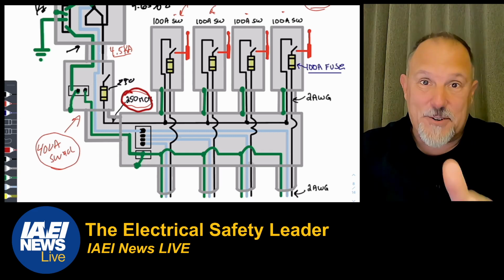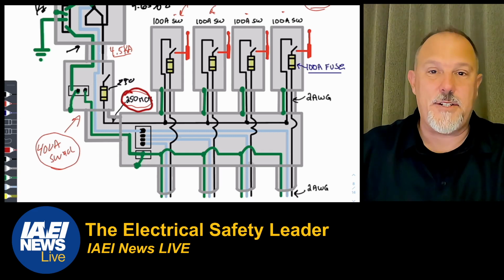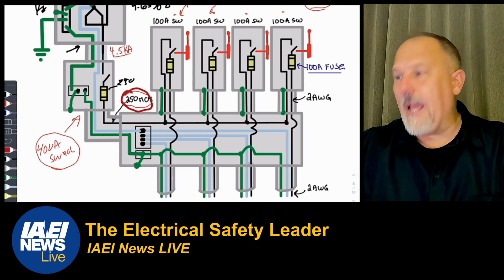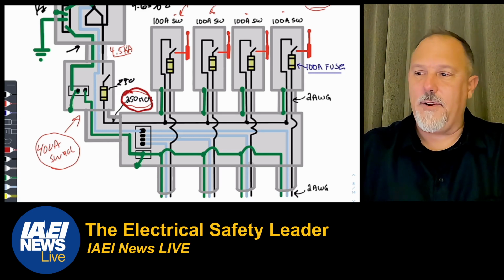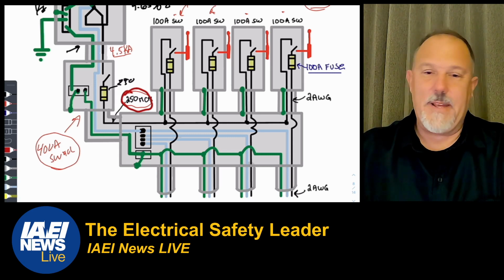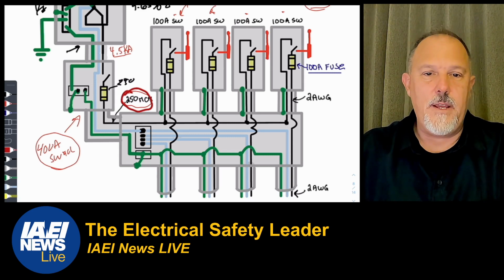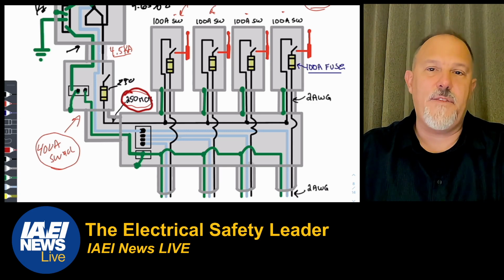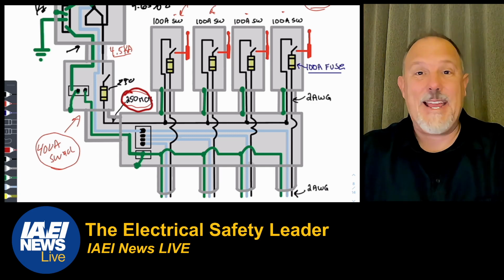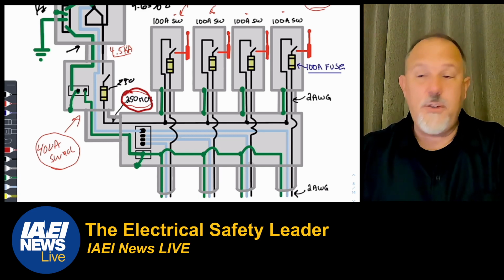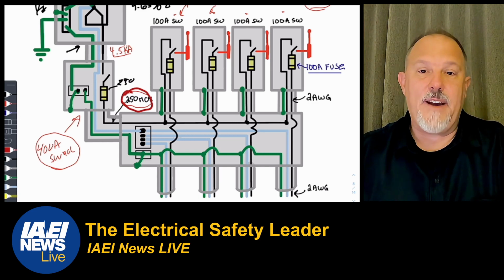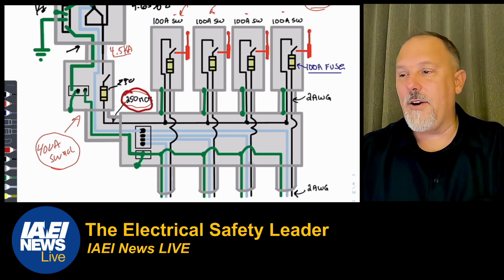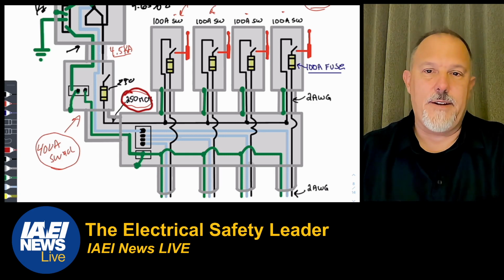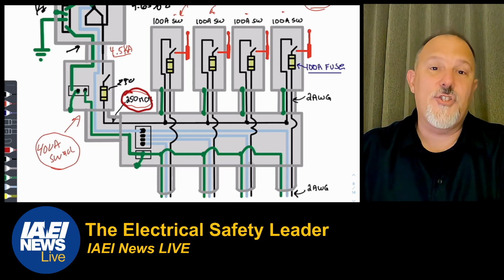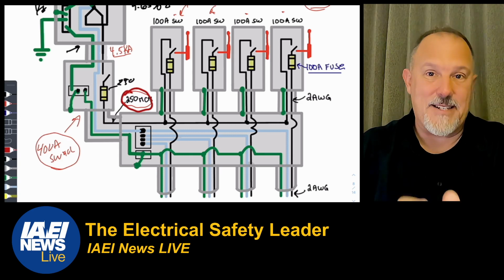And then we have to use the 75-degree C column, because we're landing on switches. And actually, we're landing on that 400 amp switch with a 400 amp fuse, but what is 250 worth? 250 is 255 amps worth of conductor ampacity. I can't put a 400 amp fuse on 250 MCM. So I would have to go up to like a 600 or whatnot, or maybe two of those. Whatever, I'd have to address my issue with ampacity, right?